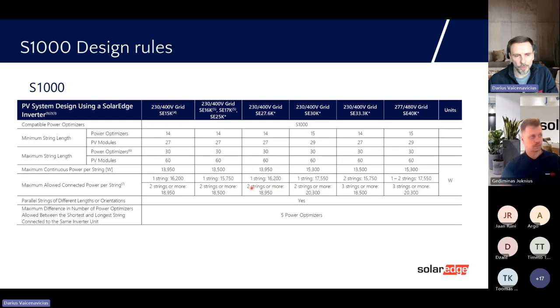But always, if you try to design projects manually, please take note that there are different requirements for different inverters. Another main rule which must be observed is that we have a maximum difference in the number of power optimizers per string connected to the same inverter or power unit. The maximum allowed difference is 5 optimizers. That means that if you have one inverter, two strings cannot differ by more than 5 optimizers from each other.